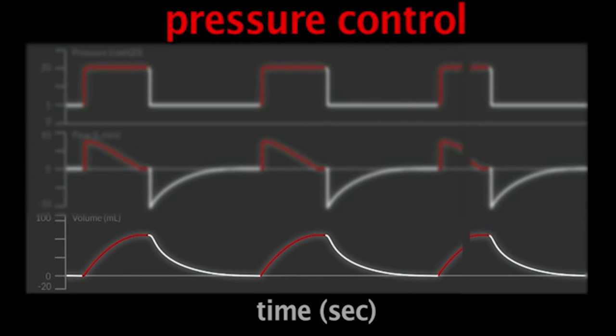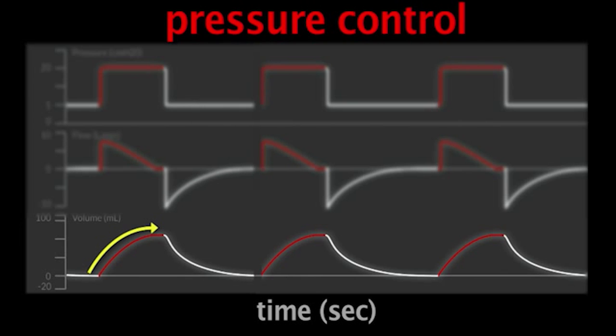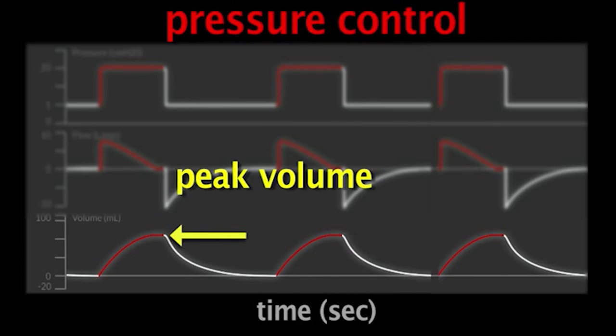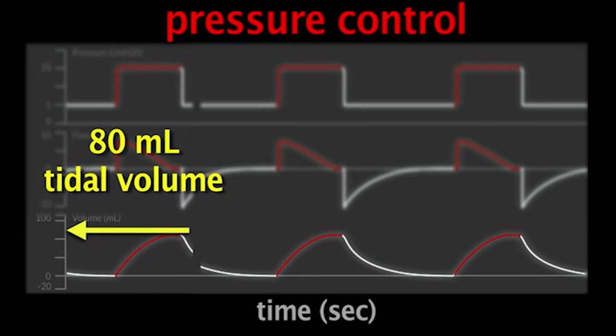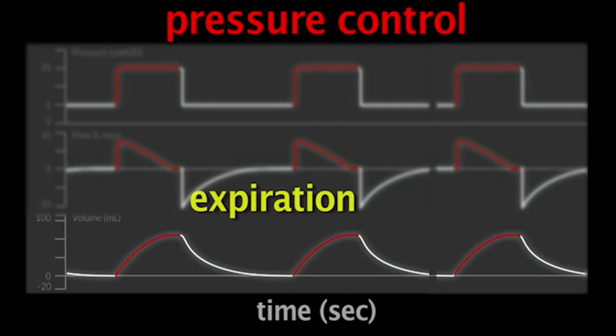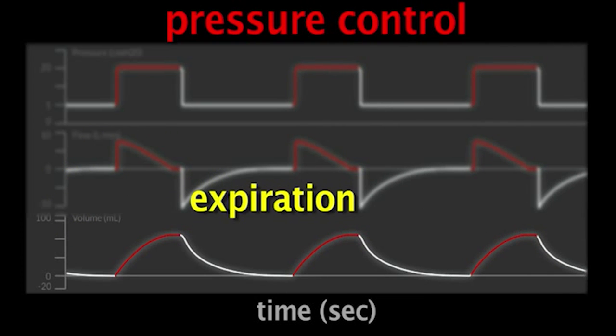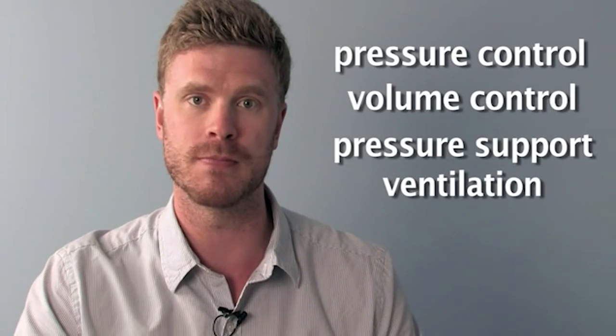Looking at the volume waveform, we start at zero mLs and increase gradually in a curved manner up to the peak volume delivered — about 80 mLs of tidal volume here. Then the ventilator cycles into expiration, the breath is exhaled, and the volume waveform gradually returns to zero. I encourage you to study normal ventilator waveforms in pressure control, volume control, and pressure support ventilation. This will help you build a solid understanding of what is normal so that when an abnormality arises you'll be able to quickly identify and treat it.